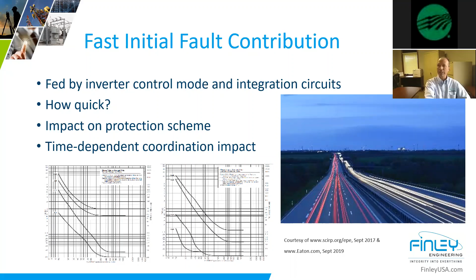So if you've been on a feeder, this will ring true. If you have a feeder with a lot of DG impact and you're seeing some trips at your substation where you've got your smart breaker, and you're downstream, you've missed some - let's just pay attention, kind of thing. So that's my point with that discussion, just recognize it.